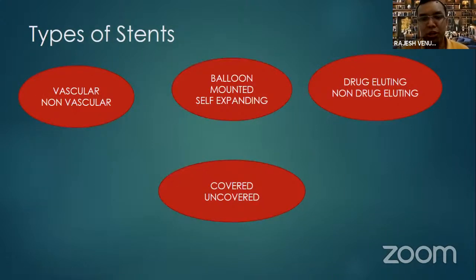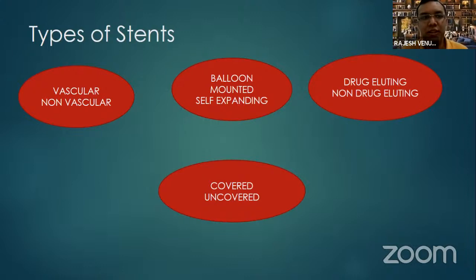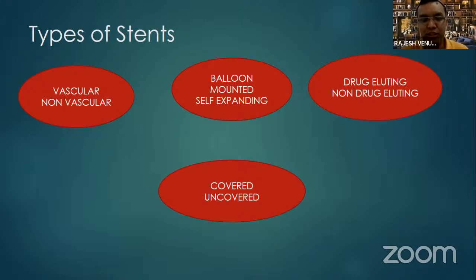Stents are broadly classified as vascular and non-vascular. A good example of a non-vascular stent is the DJ stent used for the ureters. Based on deployment, stents can be balloon-mounted or self-expanding — the biliary wall stent is an example of self-expanding. Based on drug coating, there are drug-eluting and non-drug-eluting stents; paclitaxel is commonly used to prevent endothelial proliferation and stent occlusion, increasing patency at higher cost. Based on fabric covering, stents can be covered or uncovered — covered stents are preferred for aneurysms or vessel rupture, while bare metal stents are used for other peripheral vascular interventions.